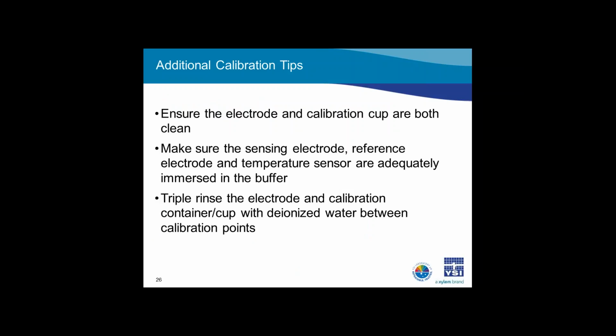Next, make sure you are adequately immersing the sensing electrode, reference electrode, and temperature sensor into the buffer. We'll talk about this again in the next slide. Lastly, as a best laboratory practice, triple rinse the sensors and calibration container with deionized water between calibration points. Before continuing with the calibration, make sure to shake off any excess DI water or dry the sensor and container with a chem wipe before placing it in the next buffer. When drying the sensor with the chem wipe, be sure to blot it so you don't accidentally damage the sensor.